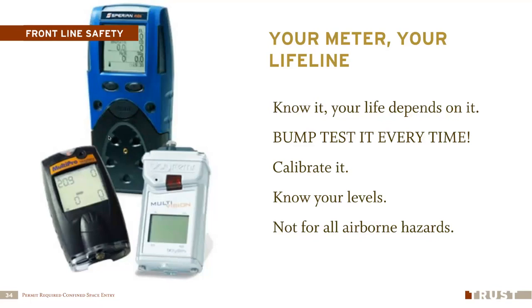I'm going to take a cylinder of a known gas, and it says right on here what the concentration is, and I'm going to expose it to the sensors on this meter. With this one, there's a pump that I use to test at different levels in a confined space. I hook it up, and if the meter reads the same as what it does on the cylinder, I'm good to go. I passed my bump test.